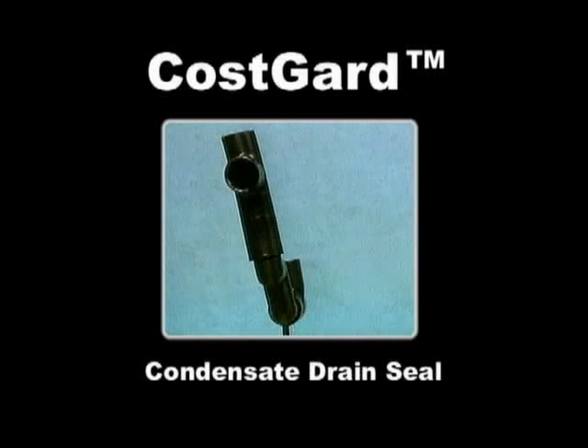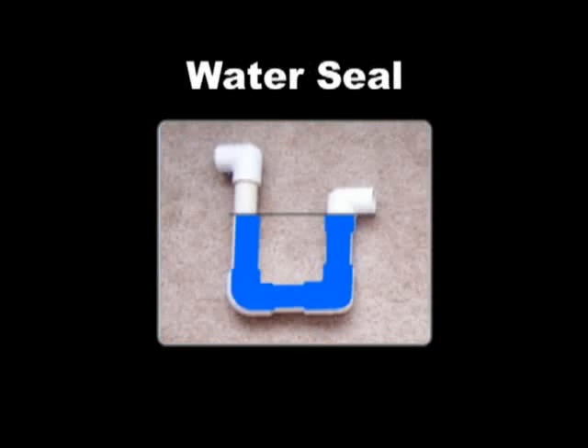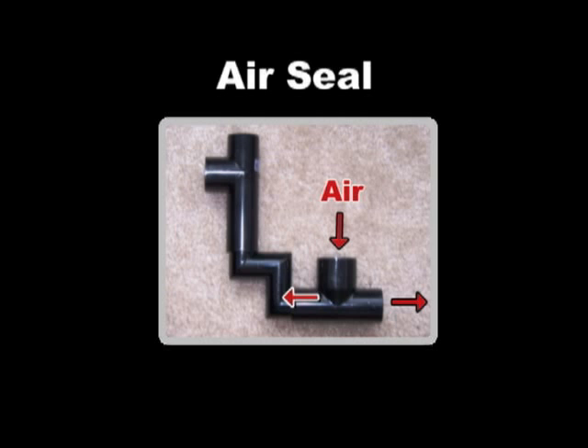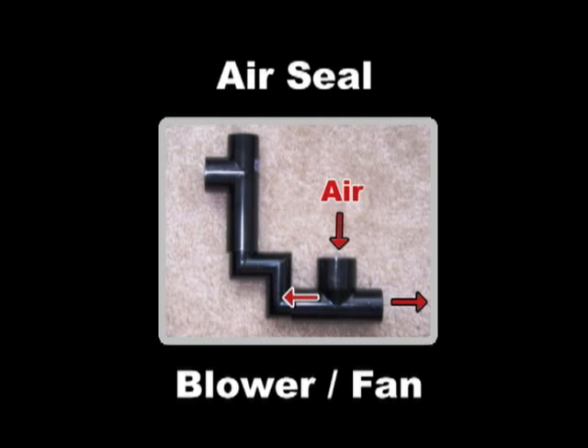You are about to learn why the use of condensate P-traps on air conditioners are unacceptable, and be introduced to an alternative that works: the CostGard condensate drain seal. The P-trap requires water from an unreliable source to form a drain seal — condensate from the cooling coil. The CostGard device uses air produced by the blower or fan to form a seal, and eliminates all the problems caused by the failure-prone condensate P-trap water seal.